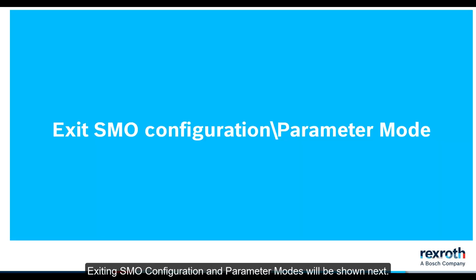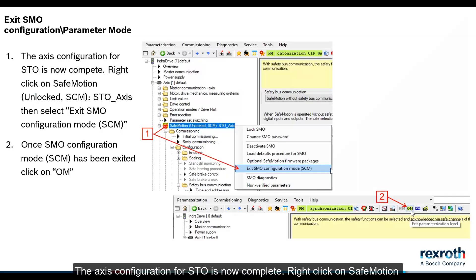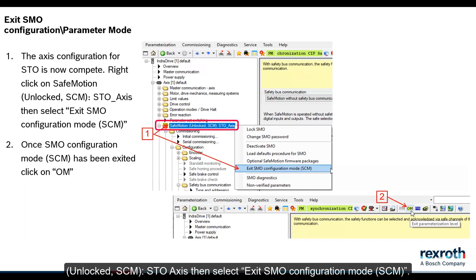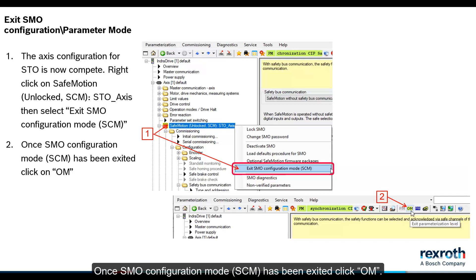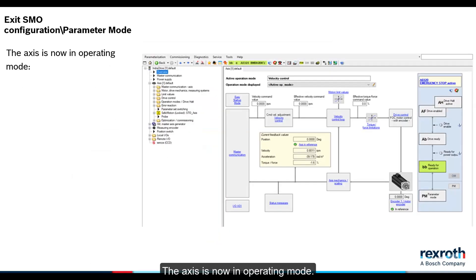Exiting SMO Configuration and Parameter Modes will be shown next. The axis configuration for STO is now complete. Right-click on Safe Motion Unlocked SCM, STO Axis, then select Exit SMO Configuration Mode SCM. Once SMO Configuration Mode SCM has been exited, click OM. The axis is now in Operating Mode.